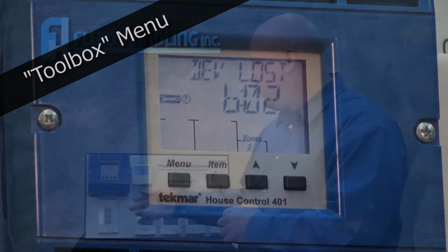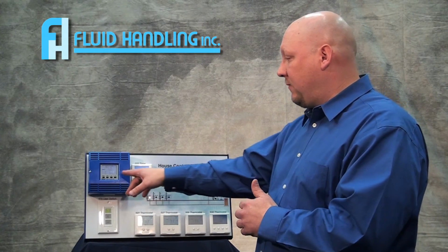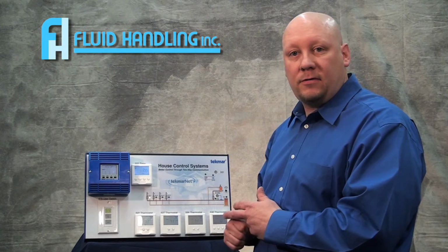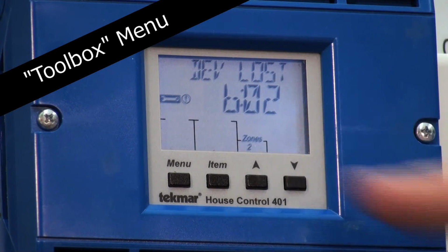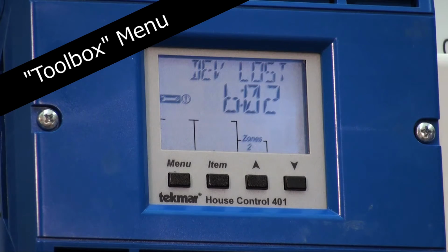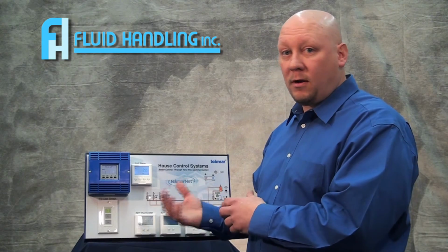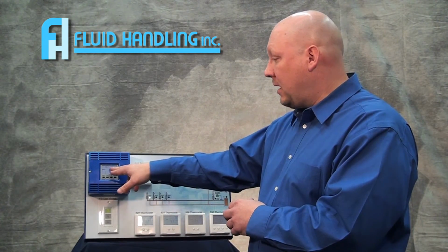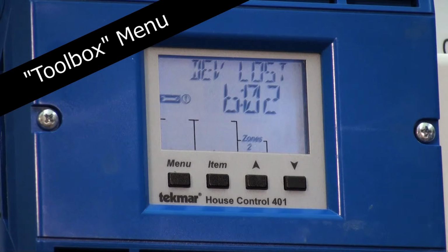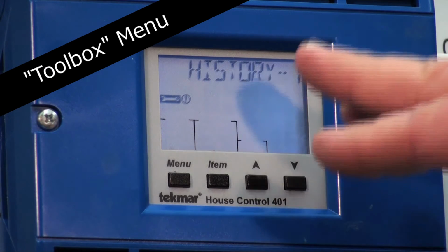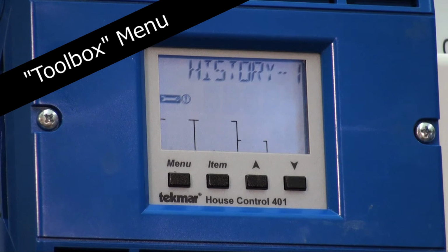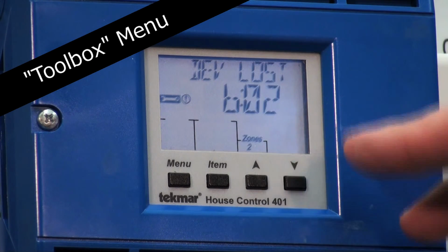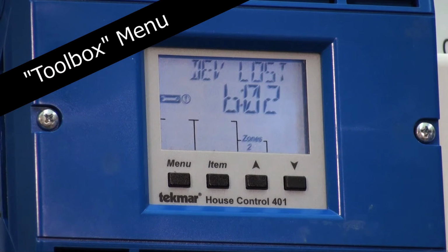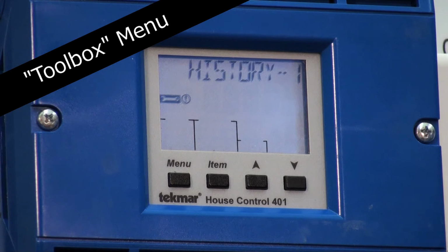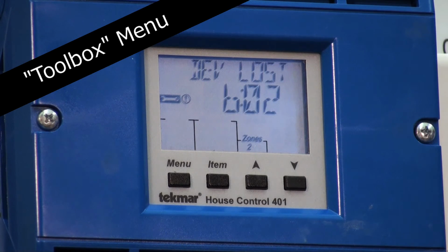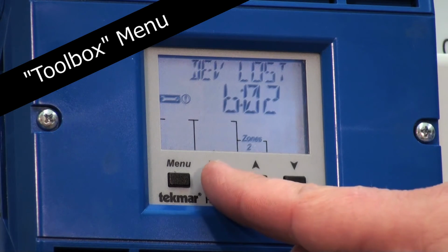And you've got history. It's showing me that I've had some devices that were lost and what device it is, which happens to correspond with the appropriate zone too. So if you disconnect the thermostat, a wire gets broke, a wire pops off, a device might get lost, but it's going to tell you which device it is and you need to figure out what's going on. When you're at this stage, if you go there because you've gotten a call and you find you've had an error message, the up and down arrows, if you press and hold them for a few seconds, the system will reset itself and that will be gone, so it doesn't keep popping up on the screen for you.